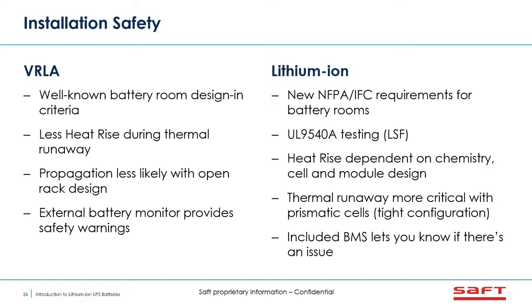Heat rise obviously is dependent on the chemistry, the cell, and the module design when you're looking at lithium-ion batteries. And thermal runaway is more critical in prismatic cells because of the tight configuration. BMS, the monitoring system or management system, is included here. So it lets you know if there are any issues going on with the battery technology.